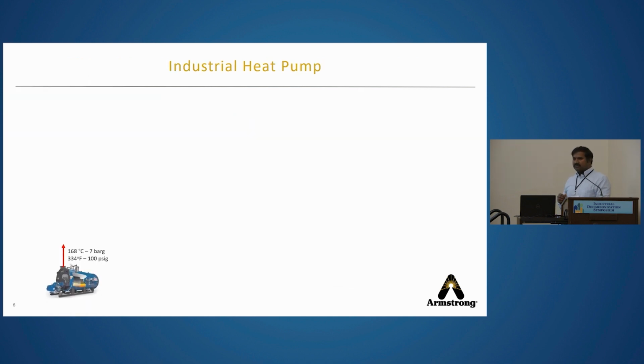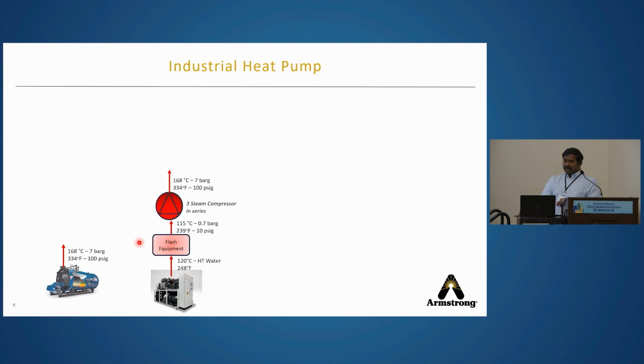Since we sell heat pumps, a very common inquiry these days is a steam heat pump. The customer has a steam boiler to generate 100 PSI of steam, and they ask us, can you give me a heat pump for 100 PSI of steam? We can do that with the help of a heat pump, a flash vessel, and a bunch of steam compressors, MVR, in series, to give up to 100 PSI of steam. Now, when we submit an offer to them, the customer feels that the CapEx is high, there is a lot of electrical equipment in this, the operating cost is high, the savings is low, and they don't prefer this particular schematic or the implementation of the heat pump system.